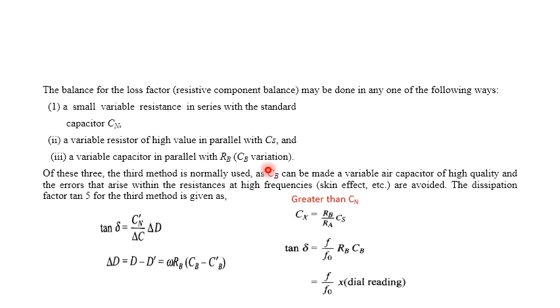Among these three, the third method is the variable capacitance in parallel with Rb. It can be made as a variable capacitor of high quality, and the errors that arise within the resistance at high frequency can be avoided with the help of the third method. Then the dissipation factor, that is tan delta, for the third method is given as tan delta equal to Cn dash by delta C into delta D, where delta D is equal to D minus D dash, that is omega Rb into Cb minus Cb dash.